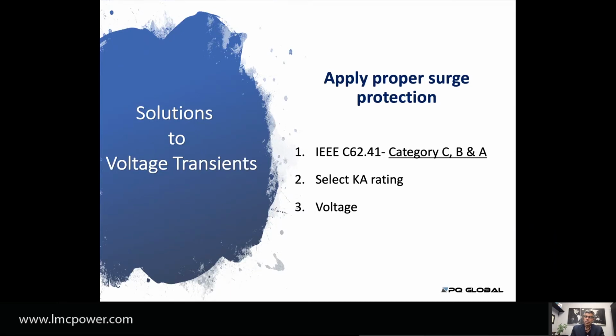Now the second point is KA, kiloamps. There's a rule of thumb that category C surge protection should be at least 150 KA. Most manufacturers make units from 150 KA to 500 KA. So anything higher than 150 KA you can put at the entrance of the building. Category B, and I'll give you some real life examples with one-line diagrams to make it more visual, is around 100 KA, somewhere between 100 and 150 KA.